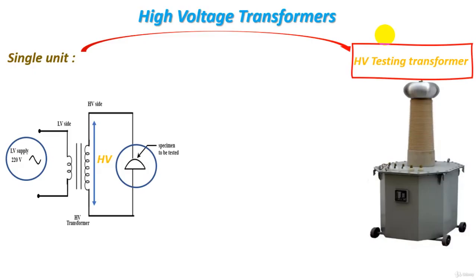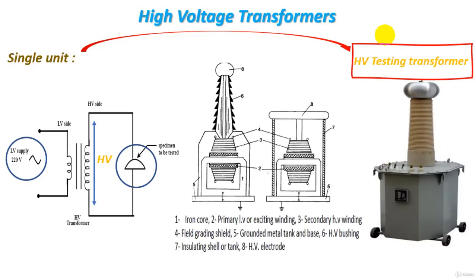Now, let's see the construction of the high voltage testing transformer. First, we have the iron core of the transformer. 2 is the primary winding or the low voltage winding of the transformer. 3 is the secondary winding or the high voltage winding of our transformer. The high voltage winding is connected to the high voltage electrode here. This high voltage electrode is then applied to the insulator to be tested.